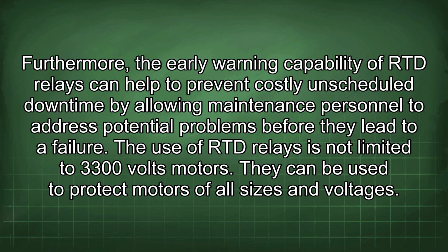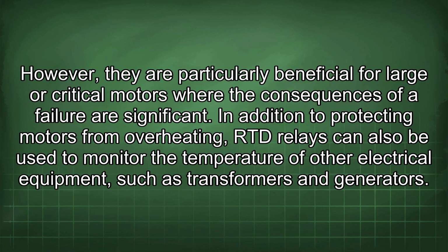Furthermore, the early warning capability of RTD relays can help to prevent costly unscheduled downtime by allowing maintenance personnel to address potential problems before they lead to a failure. The use of RTD relays is not limited to 3300 volts motors. They can be used to protect motors of all sizes and voltages. However, they are particularly beneficial for large or critical motors where the consequences of a failure are significant.